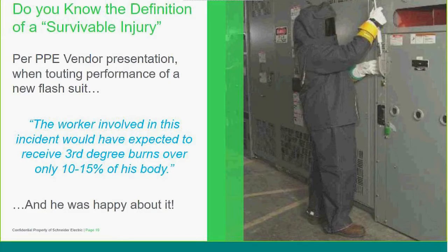When you talk about PPE, you can see the suit on there. That would probably be classified as a Cal 25 suit, and you can see quite a lot of additional clothing to provide the relevant protection. The PPE itself is non-flammable material, made of a particular type of material that can and should withstand arc blasts. As it says there, the worker involved in this incident would have expected to receive third-degree burns over only 10 to 15% of his body. That's a survivable injury.